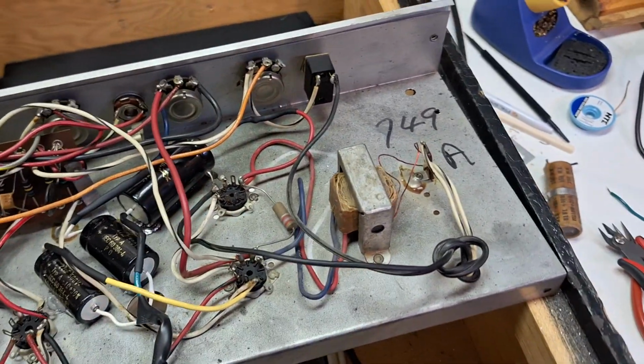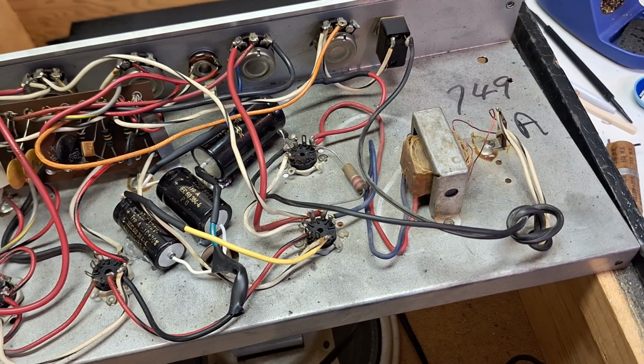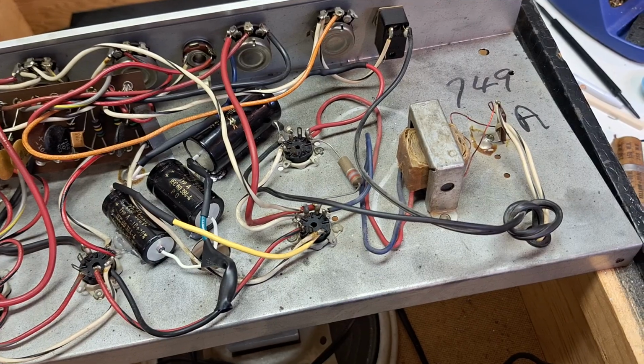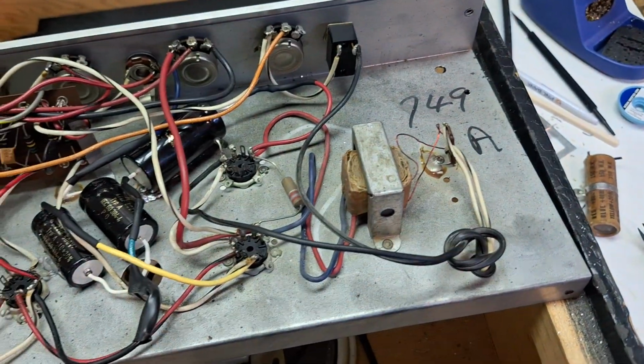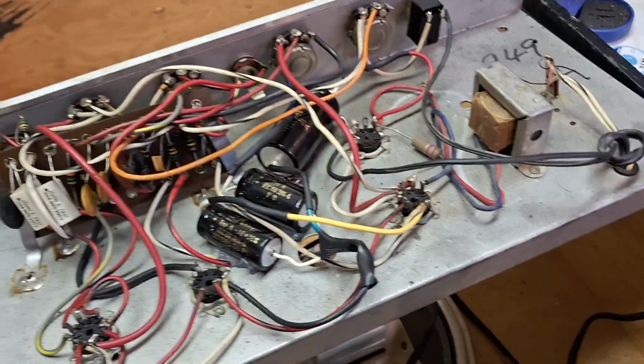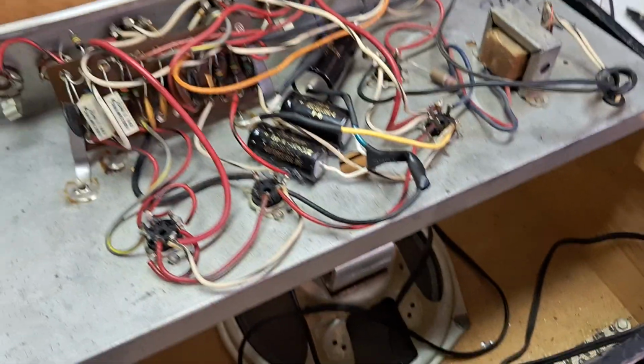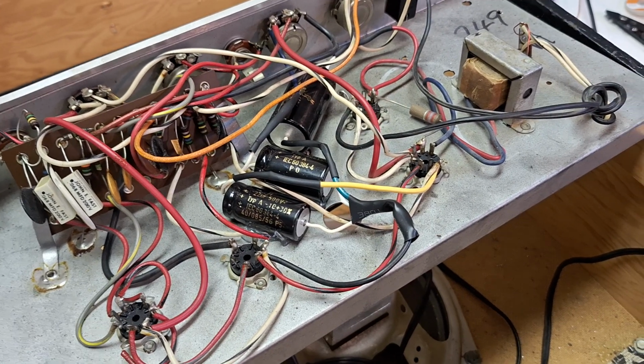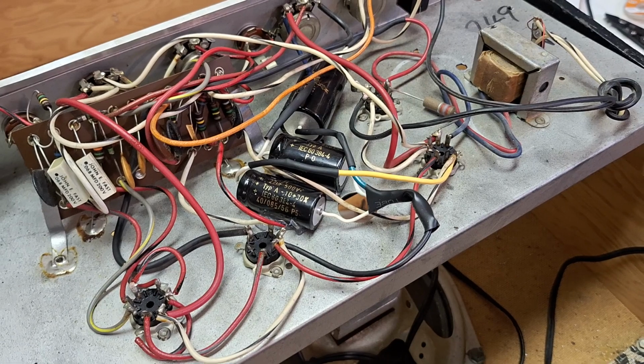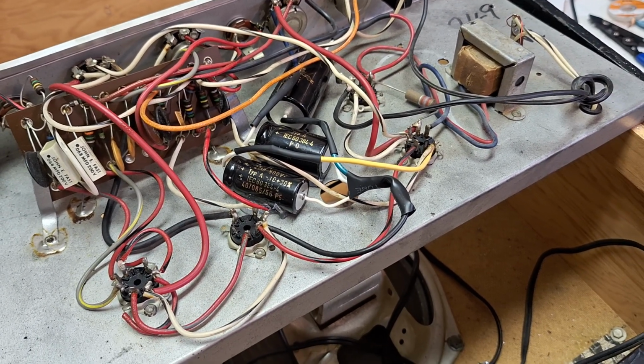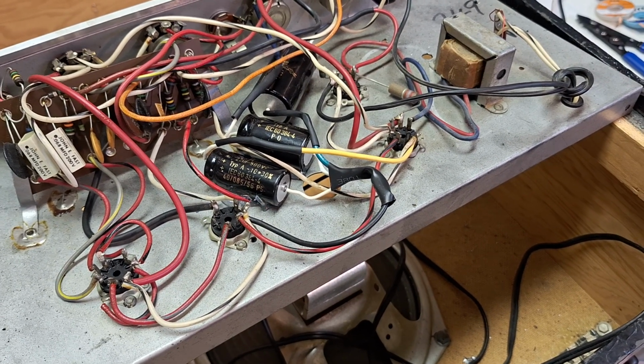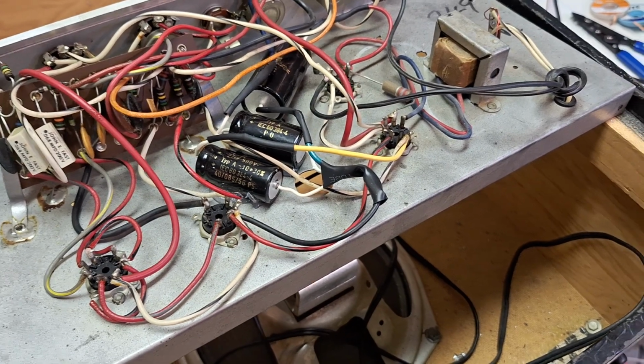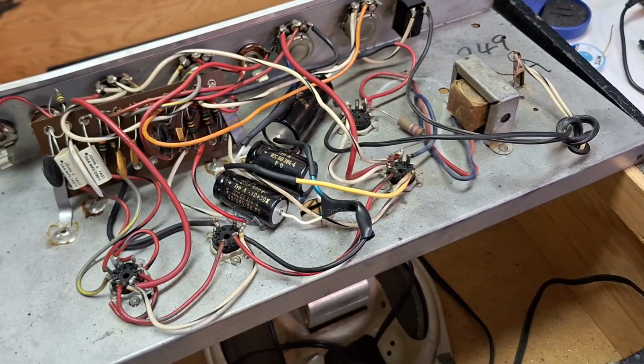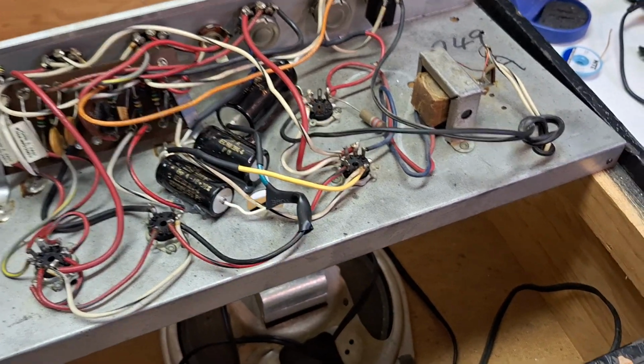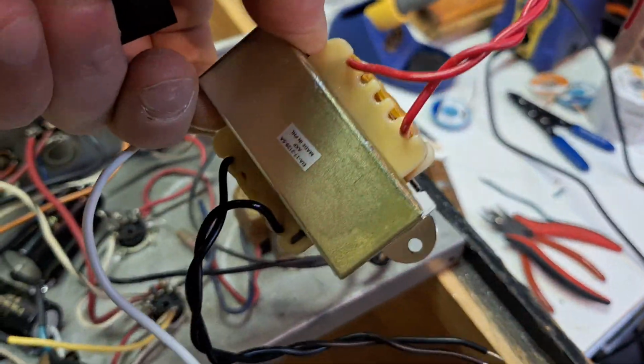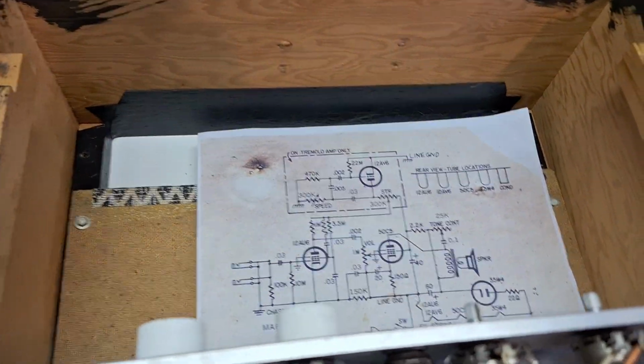Now, could we just go ahead and hook it up and it would probably be okay? Maybe, but there's the odds of having some noise, same thing with wiring it directly, like I was saying before - it could be kind of noisy. And with this rectifier issue, it could certainly pose an issue for noise. Without a load on half the cycle, it becomes an issue because the transformer becomes more saturated more quickly than normal, which puts standing DC voltage on the transformer. So there could be noise, and the transformer could get warmer than it really needs to, even hot to an extent, because it's just a one-to-one transformer. So that certainly could happen.